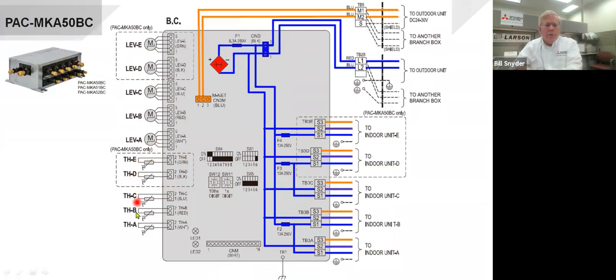Over here are thermistors. They're measuring pipe temperatures within the branch box. And then of course, the indoor units will also have thermistors for the entering, the leaving, and the room temperature on the indoor unit as well. This is where the indoor units get wired up, just like the one-to-one units wire the indoor unit right to S1, S2, and S3. Same thing, S1 and S2 is line voltage, S2 and S3 is a pulsing DC voltage.